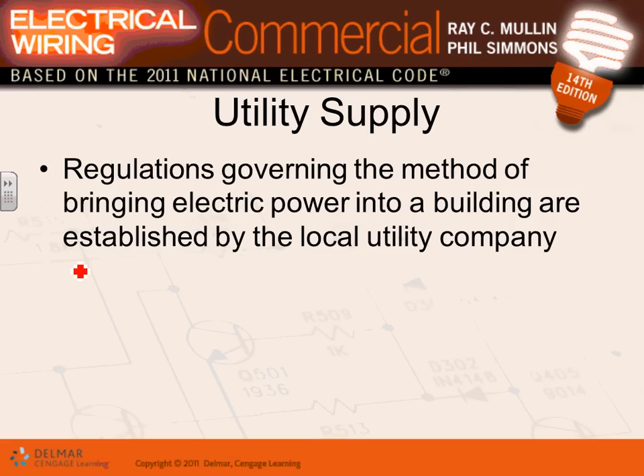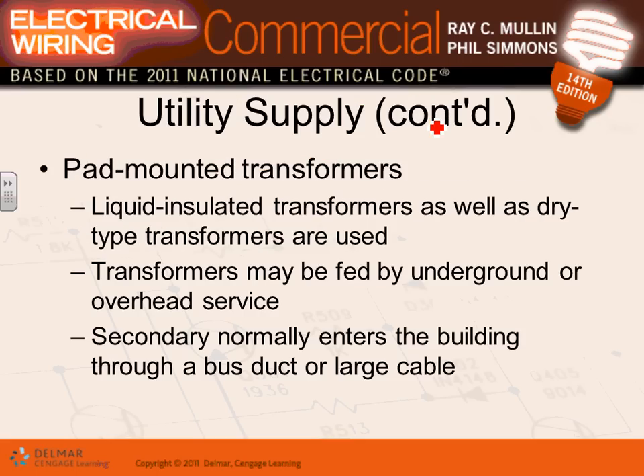Now, who decides what type of service comes to you guys is the electrical utilities. They will decide what type of transformer, 3 single-phase transformers or 1 big transformer. So be careful of that one. Most of the commercial buildings like to have something called a pad mounted transformer. You see this one in all the prints when they do them, pad mounted transformer. A concrete pad in the backyard with a big fat green looking transformer typically sitting on it. That's what the building that we designed has.